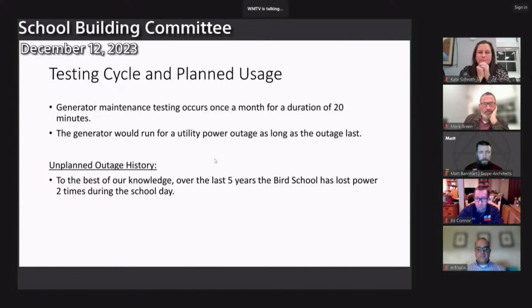Go ahead. The testing cycle planned uses the generator maintenance testing. This is your monthly testing. It's generally for a duration of 20 minutes. It would happen once a month. And it's programmed testing that can be done any day and at any time during that day. On a Saturday, Sunday, Monday through Friday, within any hour of the 24-hour period in the day.